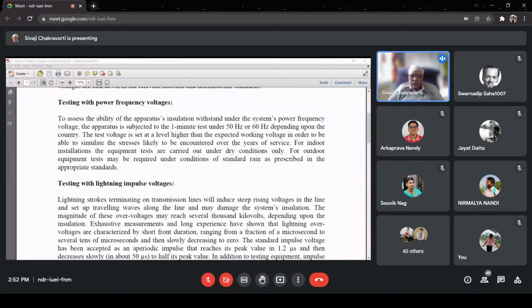So naturally, the equipment that will be used in our 50 hertz power system has to be tested. For that, we have to generate high voltage within the lab, but not for transmitting power, only for testing purposes. This we have to keep in mind. And then when I say testing, a very important question I will put forward to you: take any electrical equipment, a generator, a transformer, a motor. There will be three types of materials involved.